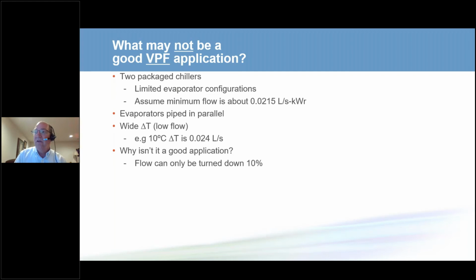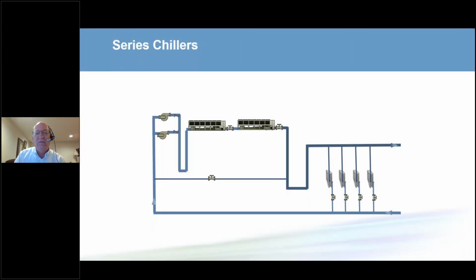Another thing we could do is consider piping the chillers in series instead of in parallel. When we pipe the chillers in series, we would want to have some bypass lines with manual valves so that if one chiller is being serviced, we don't lose both chillers. We still have the 50% capability. When we do this, we now have a larger pressure drop since we're pumping through 2 evaporators. So we have to be more cognizant of the pressure drops and the flow rates.